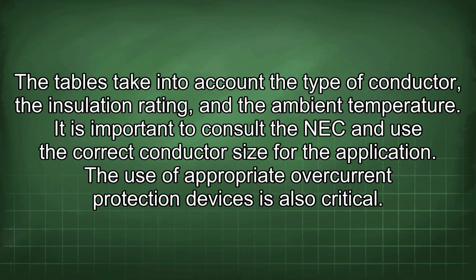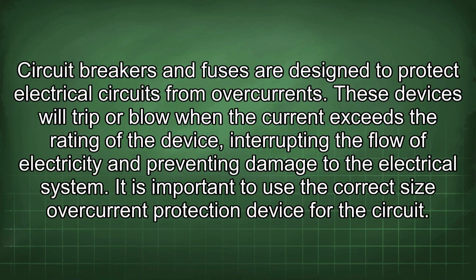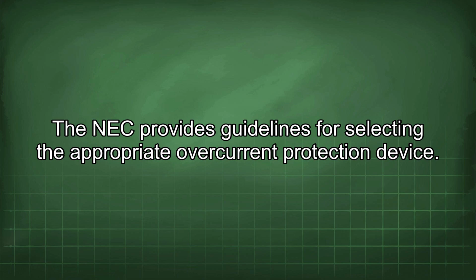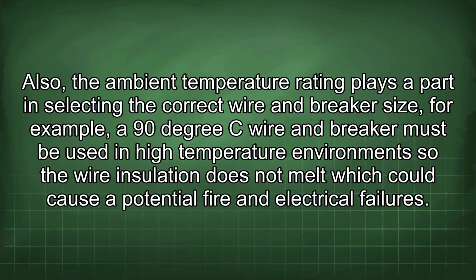The use of appropriate overcurrent protection devices is also critical. Circuit breakers and fuses are designed to protect electrical circuits from overcurrents. These devices will trip or blow when the current exceeds the rating of the device, interrupting the flow of electricity and preventing damage to the electrical system. It is important to use the correct size overcurrent protection device for the circuit. The NEC provides guidelines for selecting the appropriate overcurrent protection device. Also, the ambient temperature rating plays a part in selecting the correct wire and breaker size. For example, a 90°C wire and breaker must be used in high temperature environments so the wire insulation does not melt, which could cause a potential fire and electrical failures.